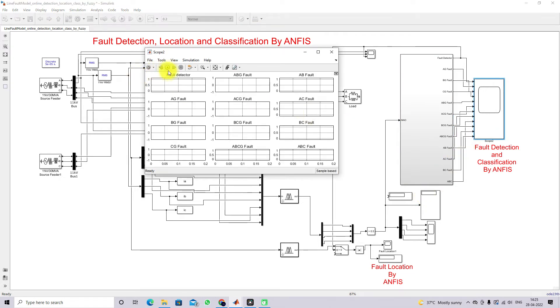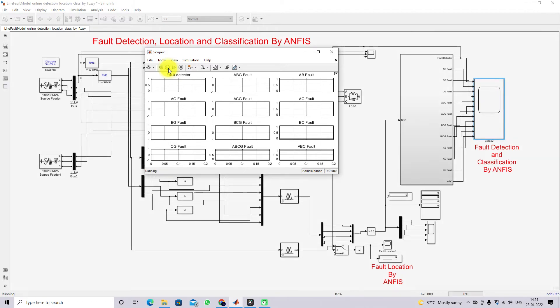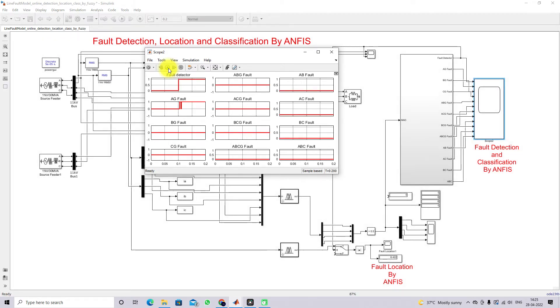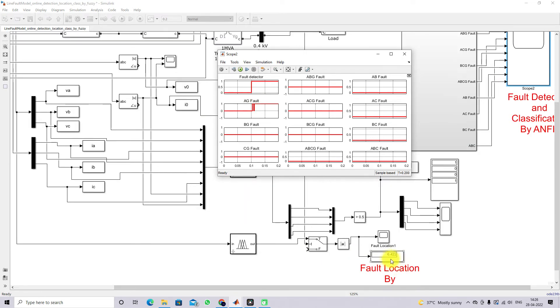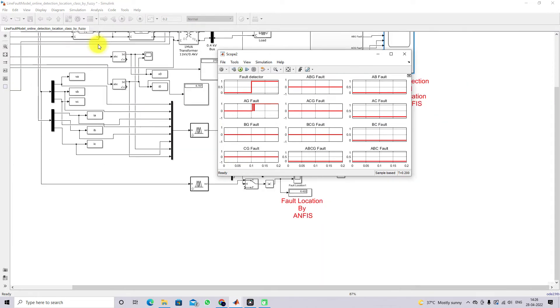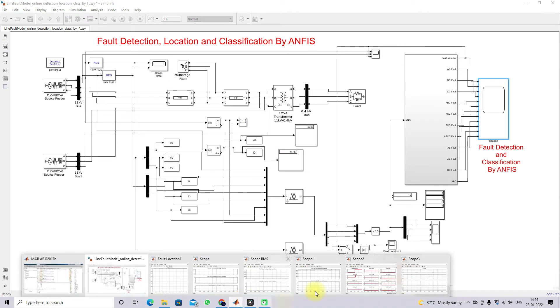Now submitting the model to check results. The fault is detected in the system. The fault created is an AG fault, and the AG fault is also detected correctly. The fault location is around 6.42 kilometers. The fault was created at 6 kilometers, and we are getting a value very near to 6 kilometers.